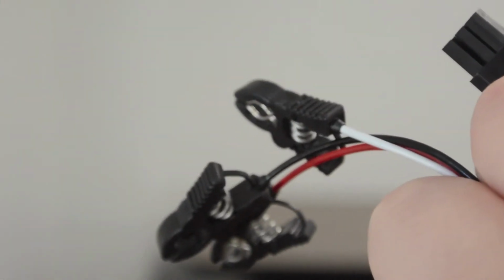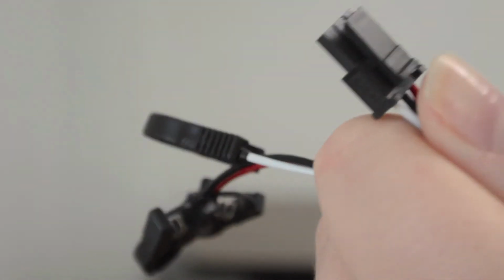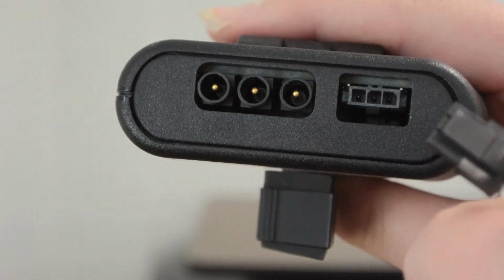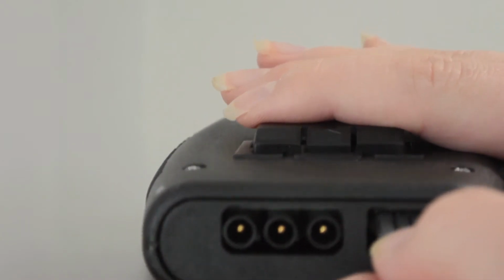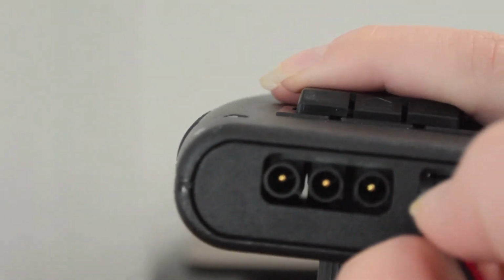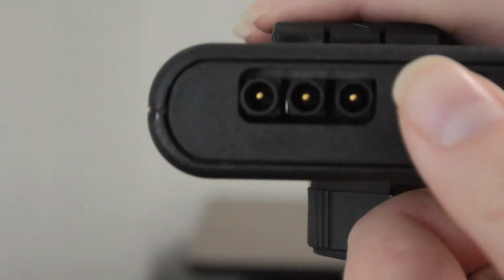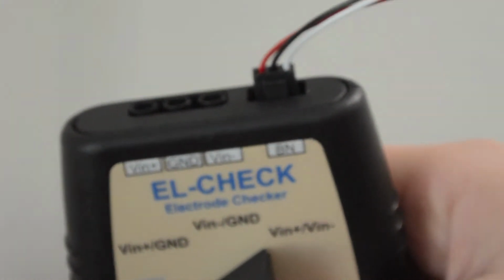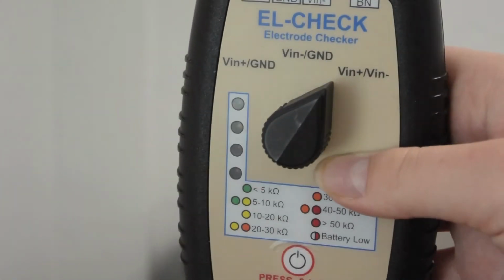Similar principle applies for BioNomadix leads. Simply take the BioNomadix lead connector and insert it into the BioNomadix lead slot on the faceplate of the EL-Check. Now that we've got our leads connected to the EL-Check, we can attach them to the subject to verify our impedance.